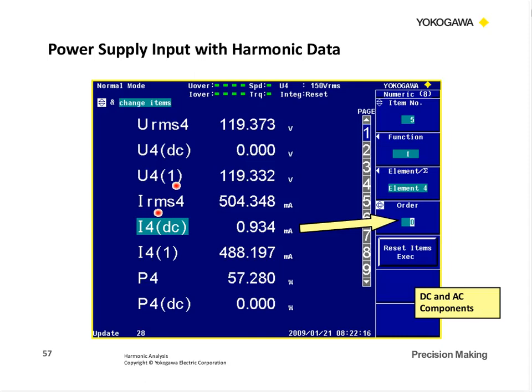And then this is the RMS value of the current, 504 milliamps. And you can see we do have some DC current available. And with the harmonic analysis, we can get that by looking at the order. So order 0 is what we define as the DC value. Order 1 would be the fundamental. And so we're looking at, in this case, order 0 for the DC value. Here's the fundamental current. Remember, the RMS current is 504, and the fundamental was 488.